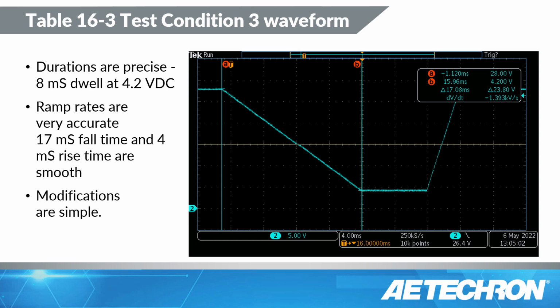If you do need to make modifications to this for whatever reason, there's possibly a customer requirement to change this, this is simple to change. You just simply change the numbers that are in this particular waveform to whatever dwell times or voltages you want to dwell at, and perform the test. It's as simple as that.